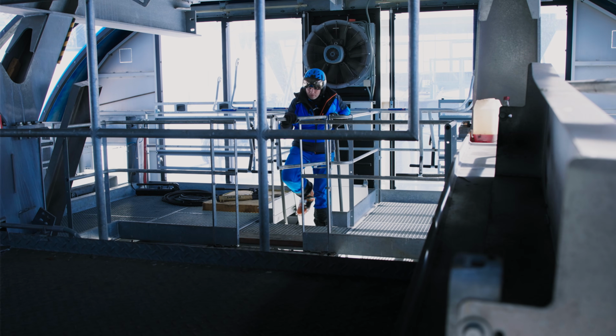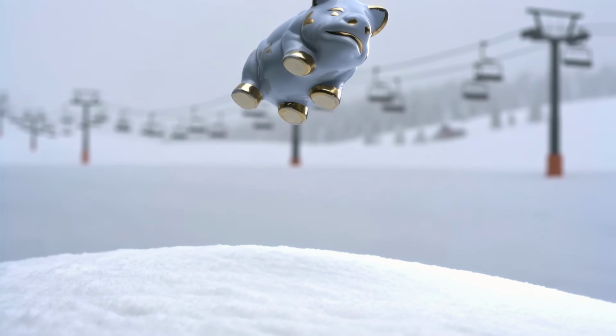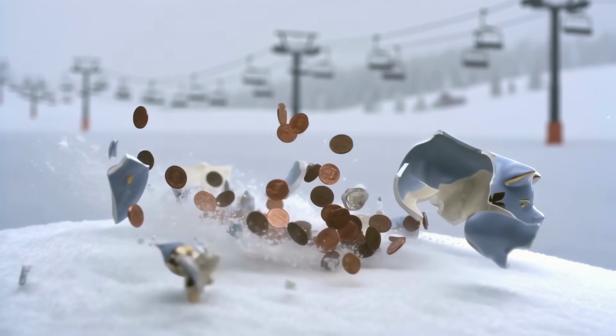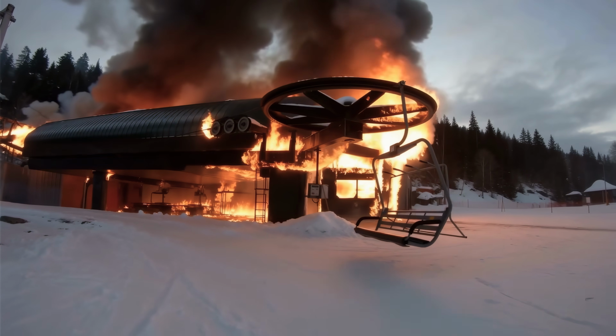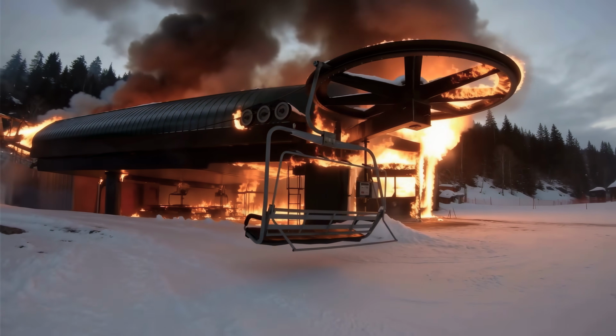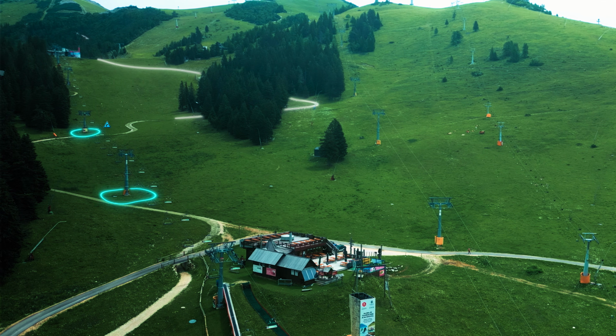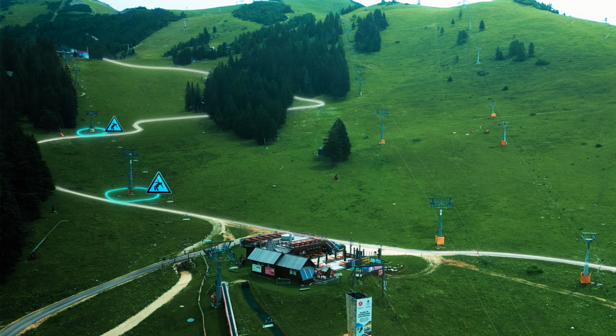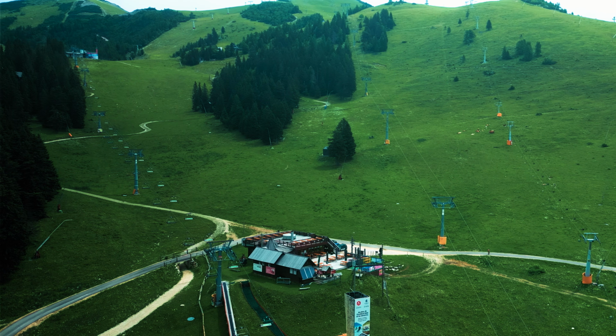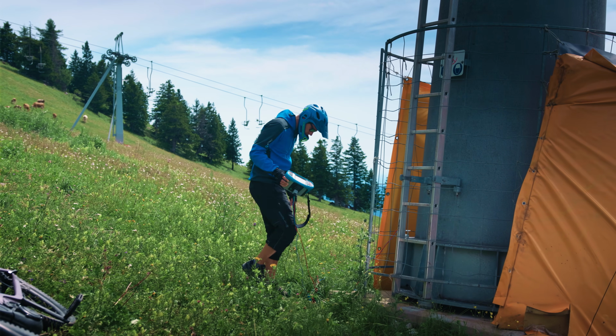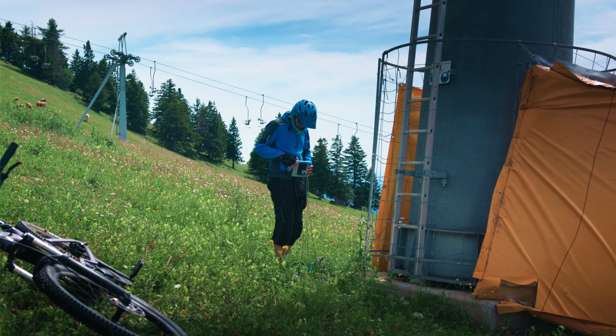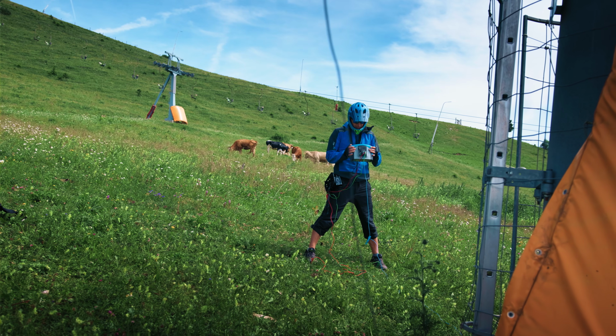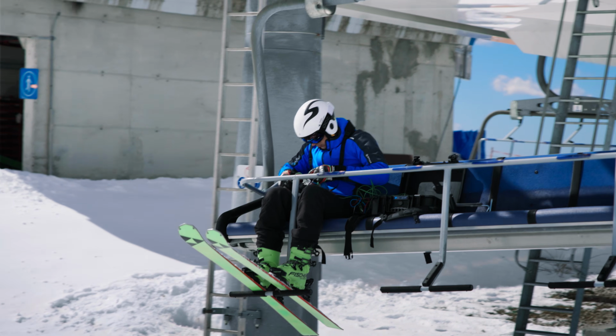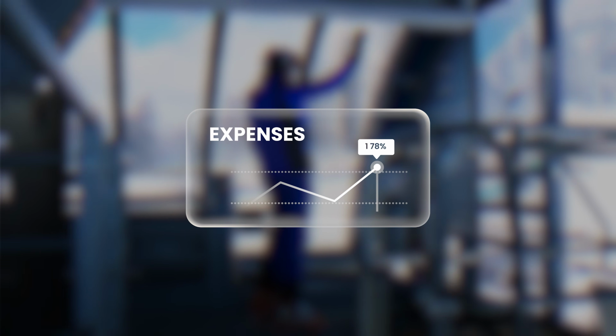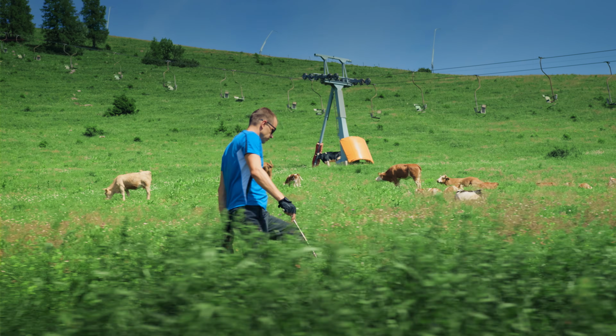Every year, lightning strikes damage ski lift cables, forcing shutdowns that lead to costly repairs and lost revenue. In severe cases, entire installations can even catch fire. During summer, inadequate grounding adds another serious risk: dangerous touch and step voltages around ski lift infrastructure. To ensure safety and efficiency, testing should focus on touch and step voltage measurements, since using incorrect methods not only wastes time and inflates costs, but also compromises safety.